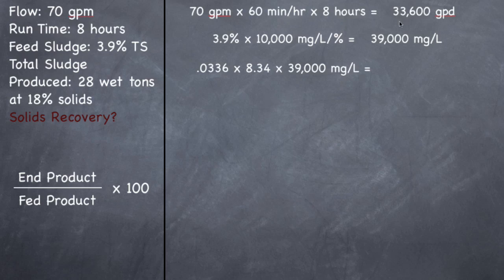Converting to MGD gives 0.0336 MGD. Then 0.0336 MGD times 8.34 times 39,000 milligrams per liter equals 10,929 pounds fed. This number assumes the cake is 100% dry — if you spread this cake out and removed all the water, you would have 10,929 pounds fed for the whole day, 100% dry.